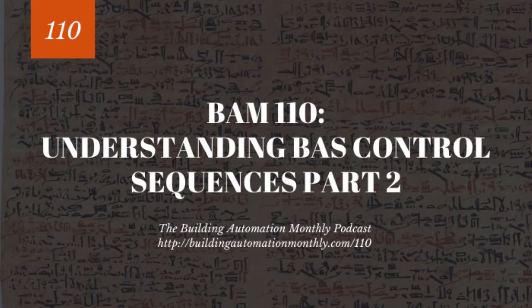Well, what some folks will do is say, oh, okay, then my minimum set point for my VAV box should be 50 CFM. But here's the problem with that. Unless you have a 100% outdoor air unit, you're not getting 50 CFM of outdoor air.